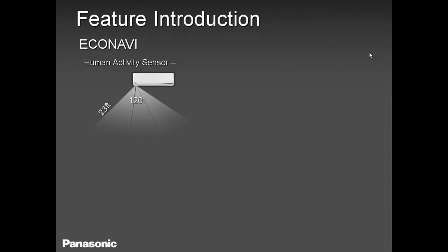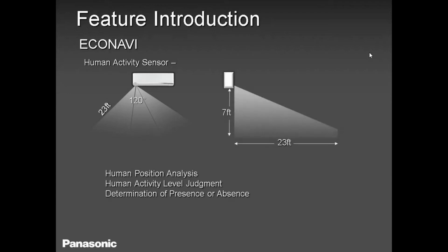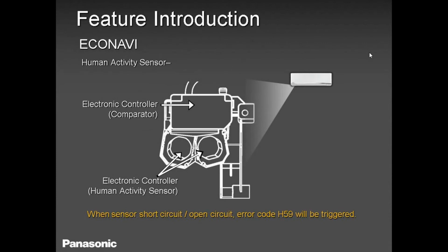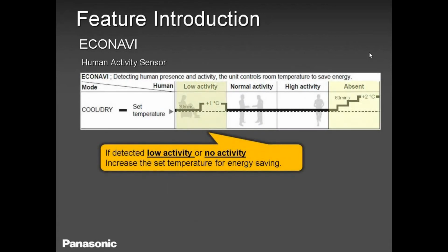Okay, now let's talk about the Econavi sensor. The Econavi sensor is not present in our Nano X unit. The Econavi sensor is present on our multi-zone indoor head, which I mentioned earlier at the beginning of the training, that the indoor units that work on multi-zone can also be installed on a single zone basis. The only difference between the two is the Econavi, and obviously no built-in Wi-Fi, and it can operate down to minus 15. Okay, I'm sorry. It can work below minus 5.